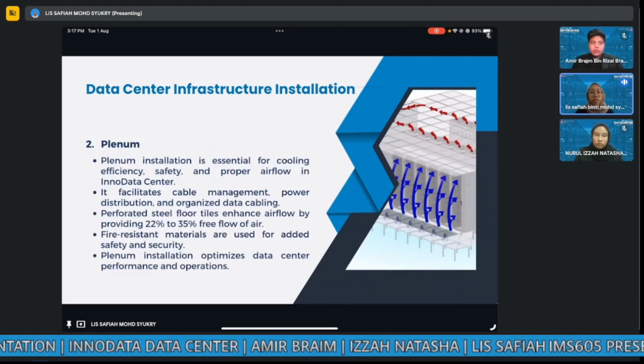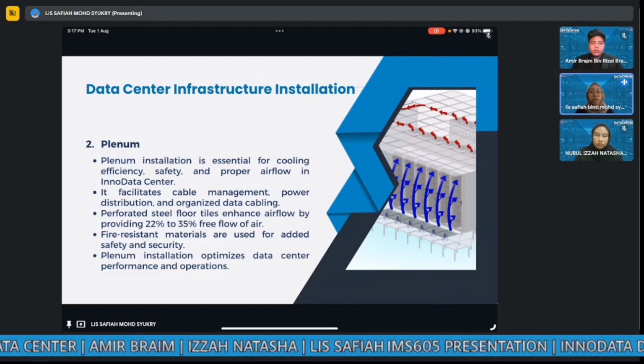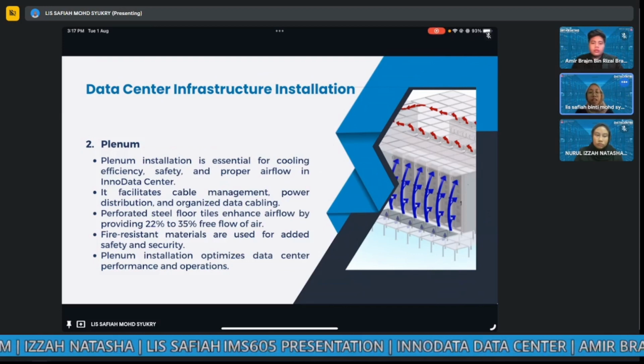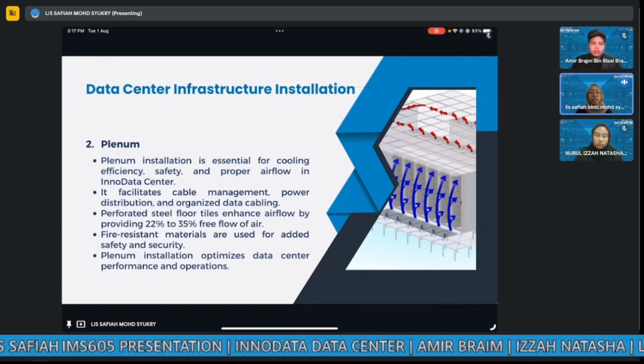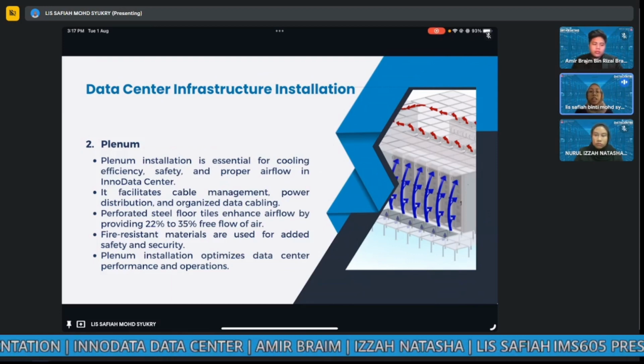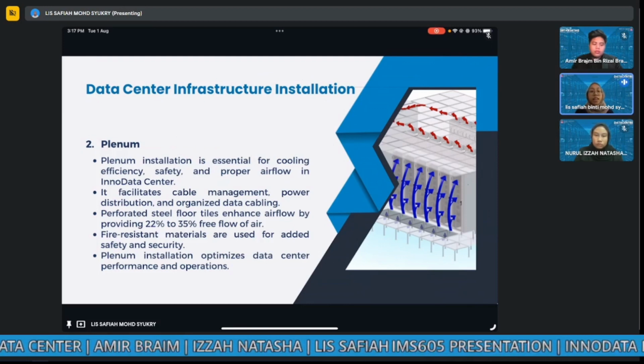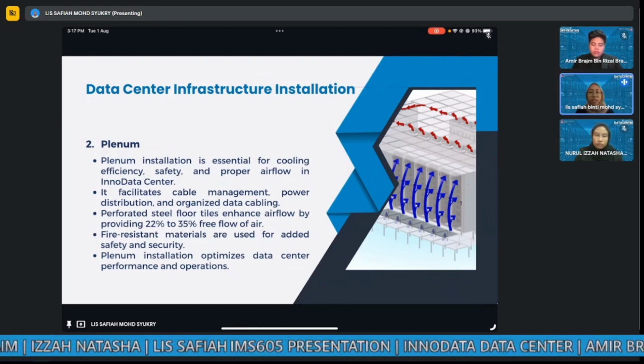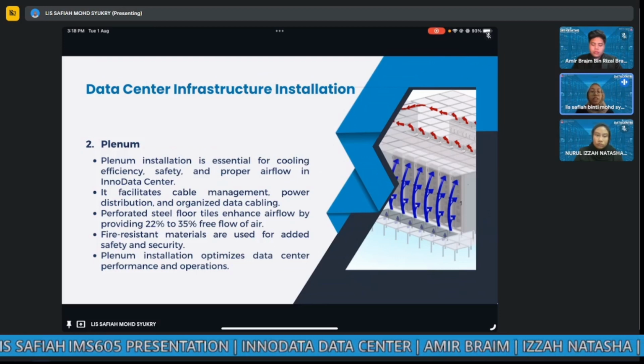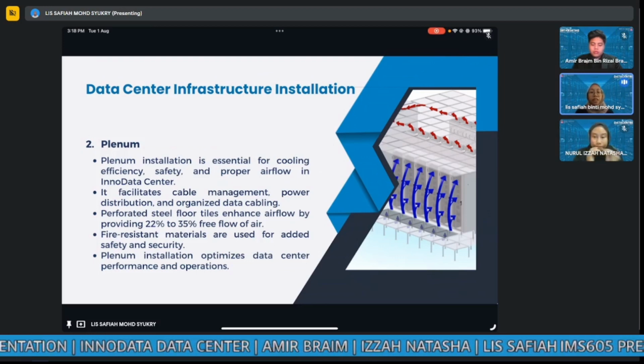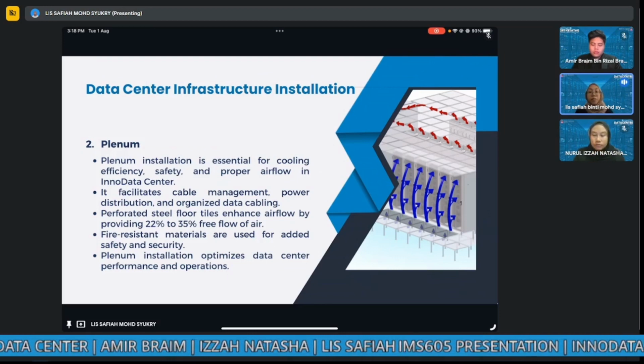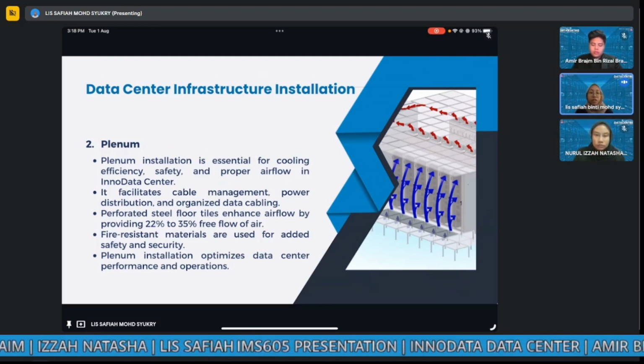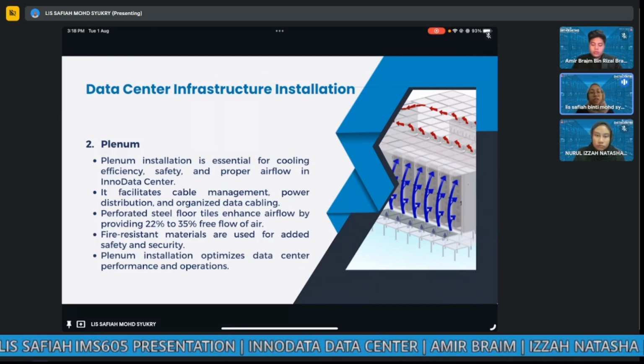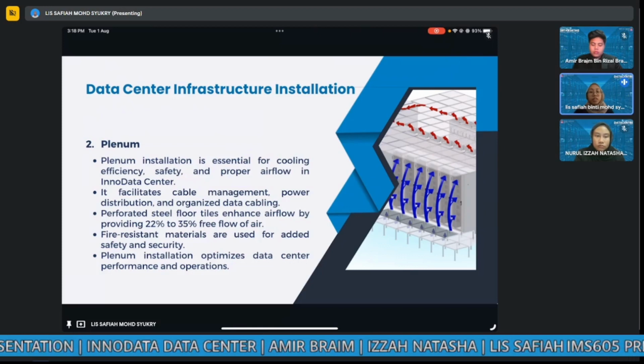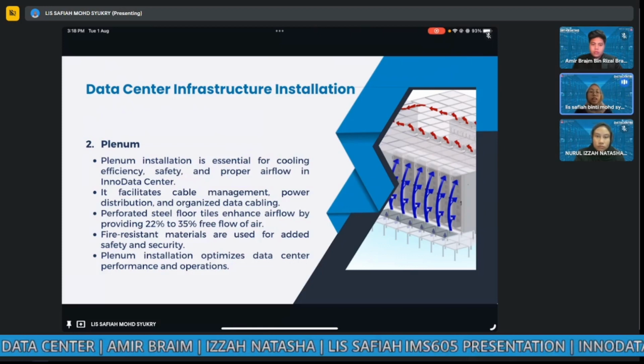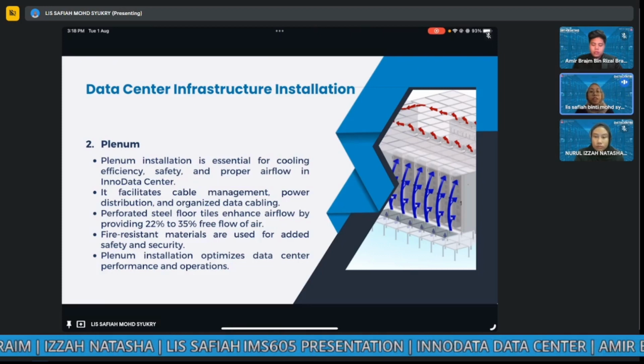Next is the plenum. The plenum plays a crucial role in cooling efficiency and safety. It allows for proper airflow, ensuring our data center stays cool and operational. Additionally, it facilitates efficient cable management and handles power distribution effectively. This organized approach streamlines our operations. To optimize airflow, we use perforated steel floor tiles, providing 22% to 35% free air flow throughout our data center. The plenum is constructed with fire-resistant materials, minimizing risk and ensuring a secure environment.